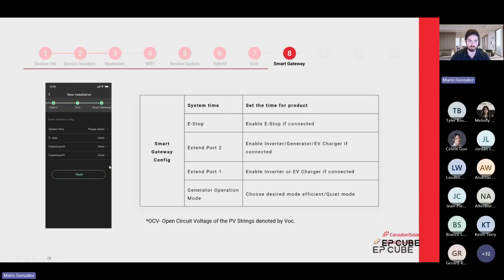Extension port 1 and 2, here's where you enable them. Very important: if you have an AC string, a generator, or whatnot, always make the physical connection first before you activate these ports, because activating them makes the gateway provide 240 volts to the extension port terminals, and you don't want to work with live electricity. So make sure all terminations are done before you activate the ports.